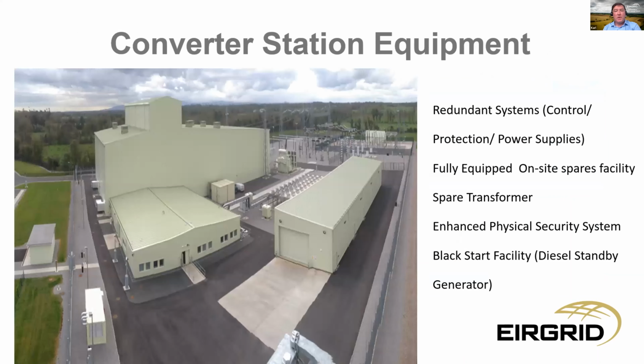There's a lot of equipment at the converter station designed with redundancy to operate for over 8,584 hours of operation in a year. To realize this, full redundant control and protection and power systems are required, and this is located in the building. Sorry, I'll just move something here. This building here. The MACH2 controller is at the heart of the control of the interconnector responding to system events.